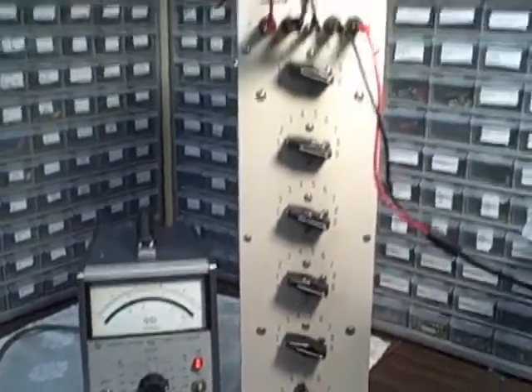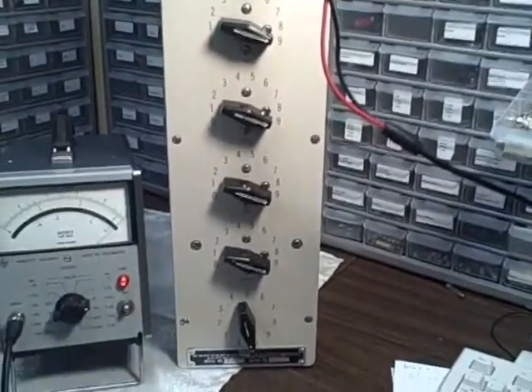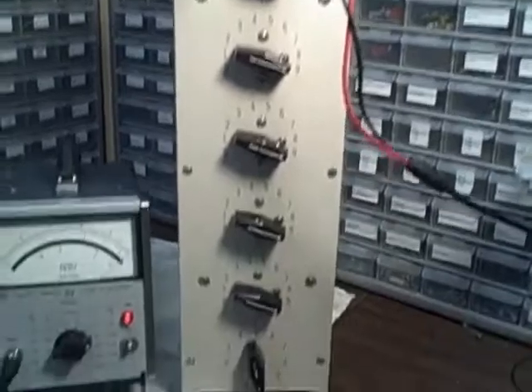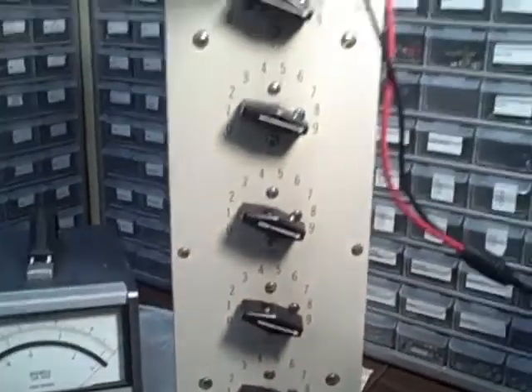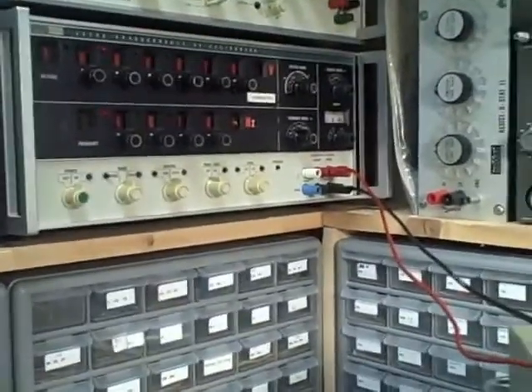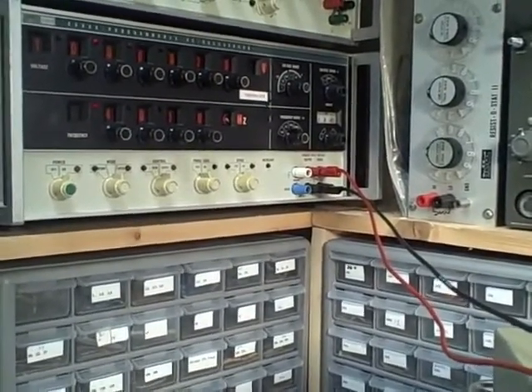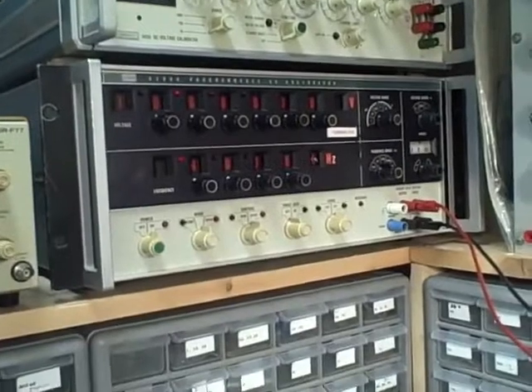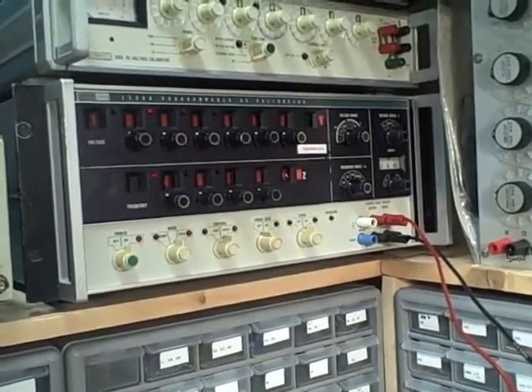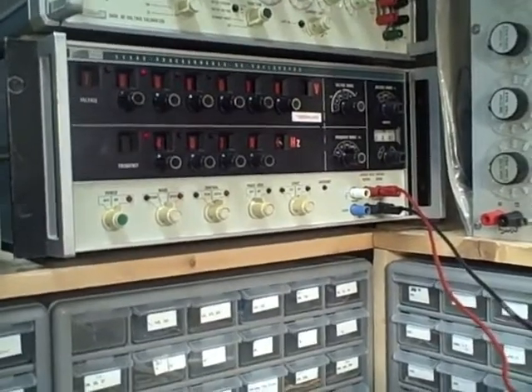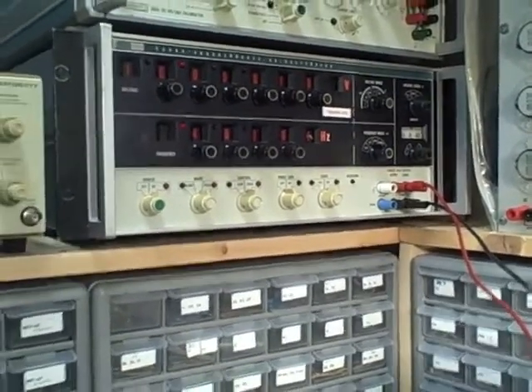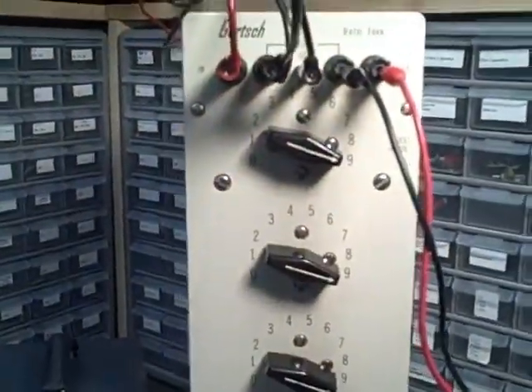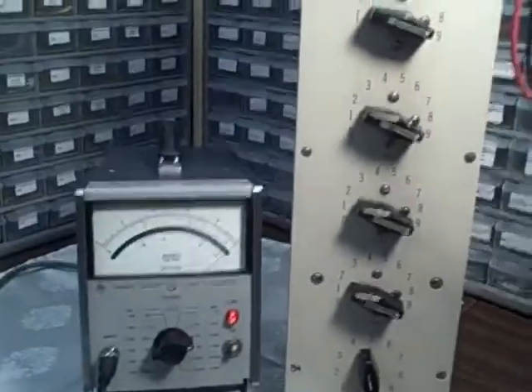Alright, I've hooked the Hewlett-Packard 400E up to this Gertsch ratio transformer. The ratio transformer gives me easy access to dial in the voltages I want to measure with, and I'm feeding in my calibrating voltage from this Hewlett-Packard 5200A calibration unit back here. We're feeding 10 volts AC at 400 hertz right now, and it reads 10.00000 volts. So with that voltage coming in, I can use the ratio dials on the Gertsch to dial in whatever voltage I want to read on the meter.